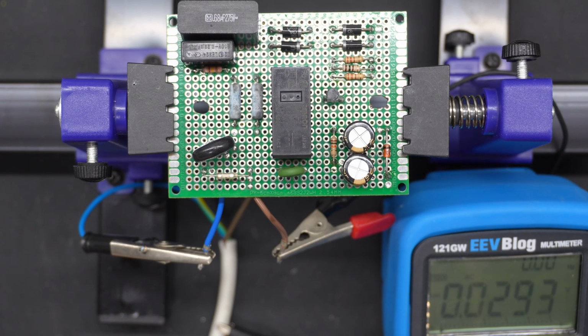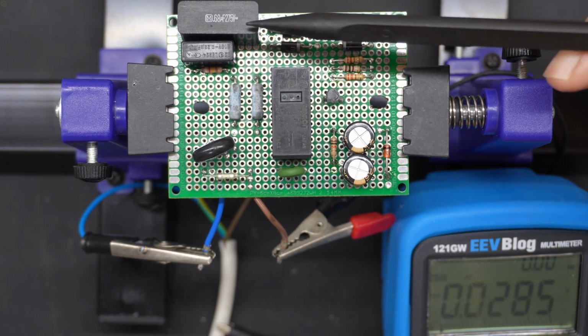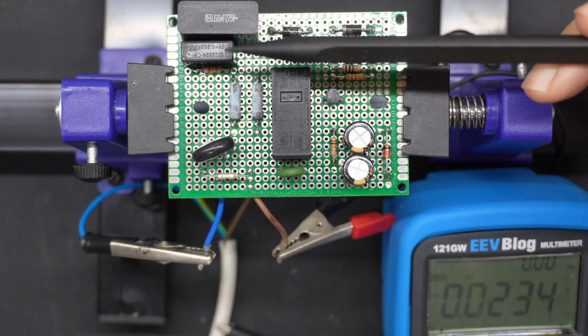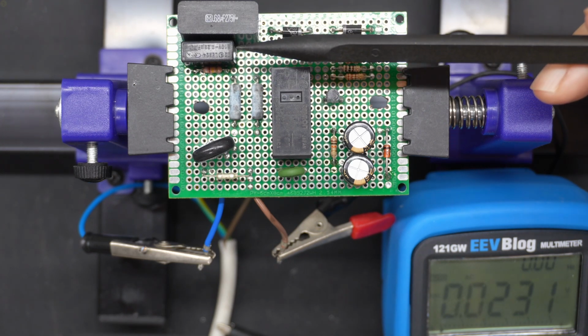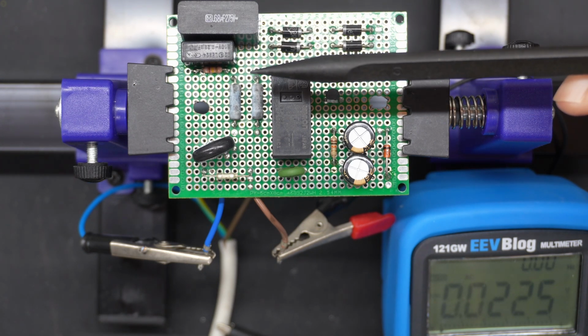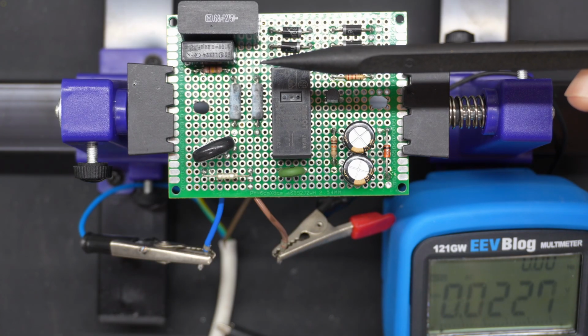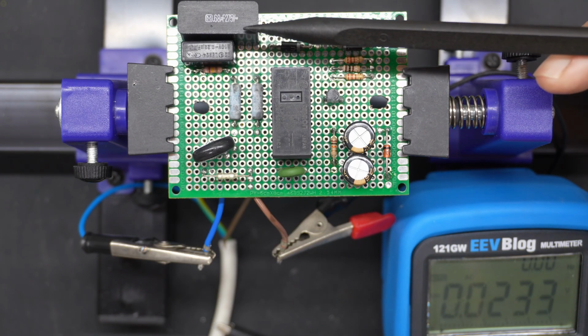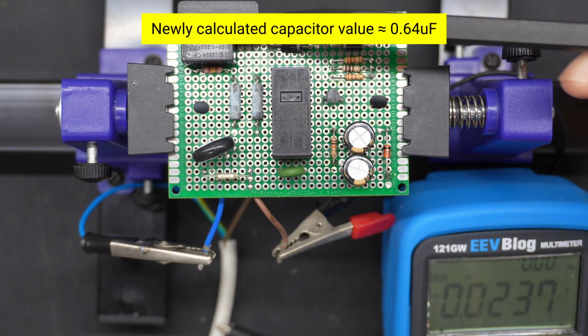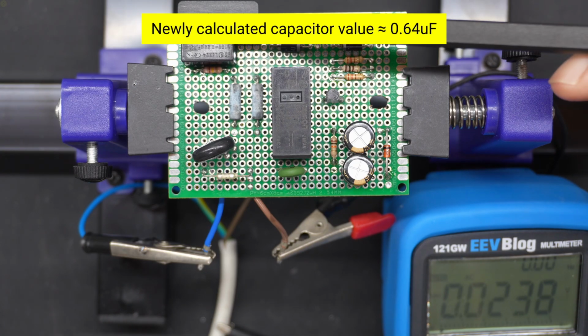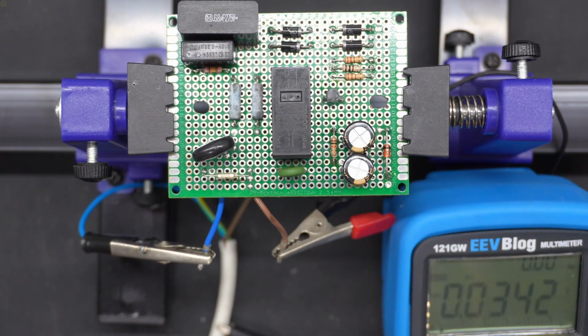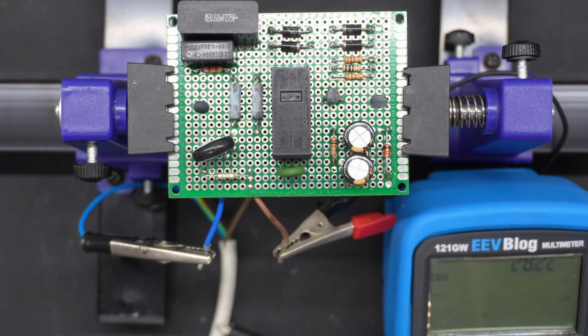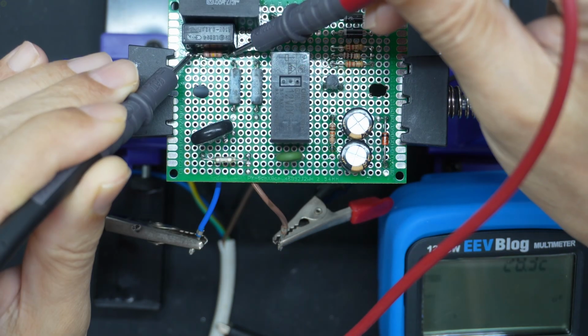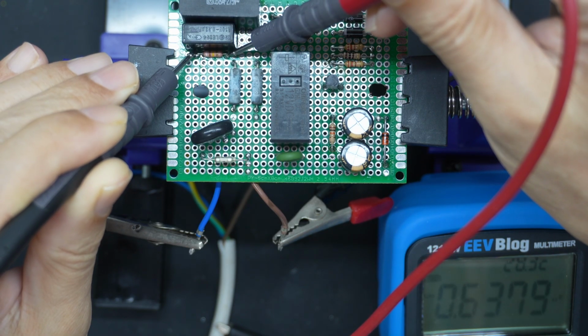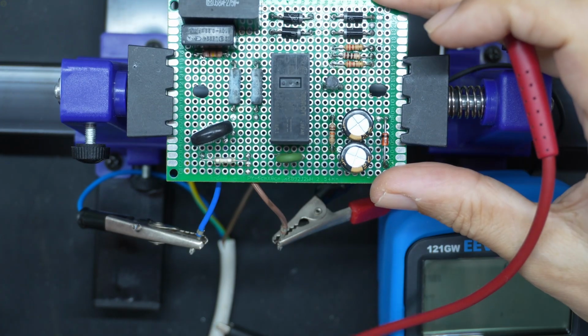Okay, we are back, made some changes. I changed this capacitor because the overall capacitance was a bit low last time, only reading about 0.5 microfarads, and it's supposed to be up into 0.6. I found I'd just put the wrong capacitor in, so I replaced it, and now if I measure capacitance, it's 0.634 microfarads. That should do the job.